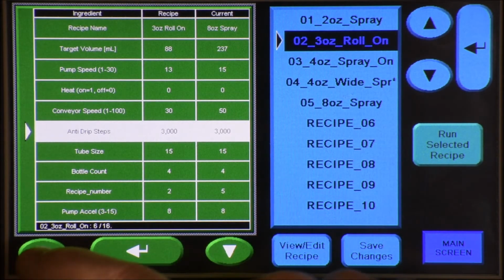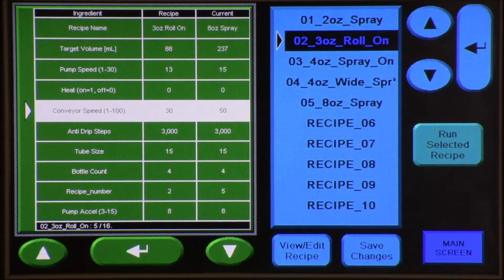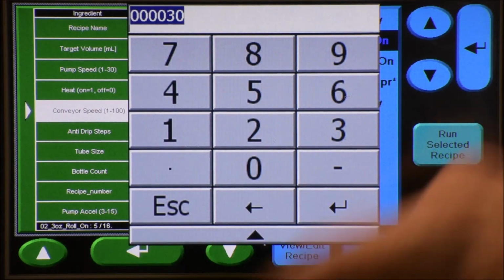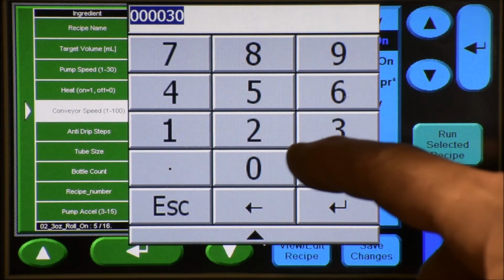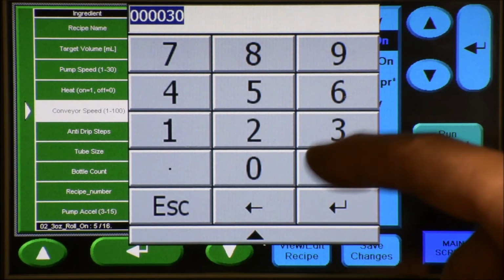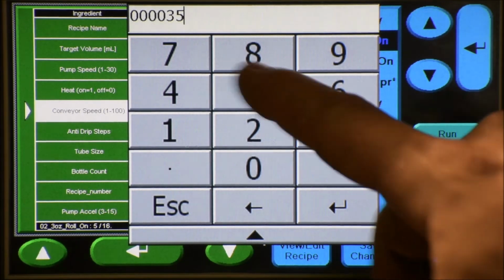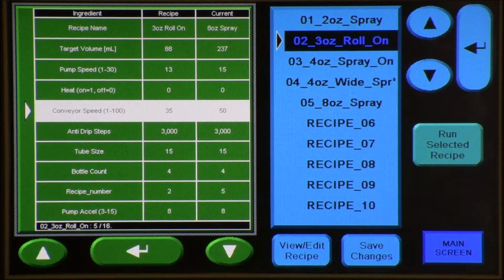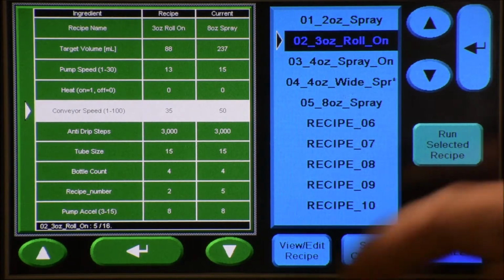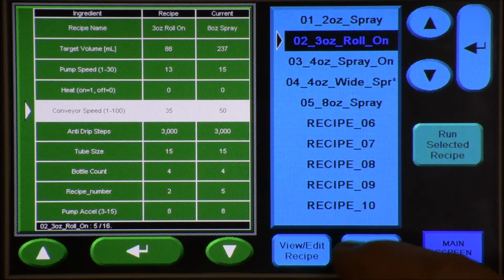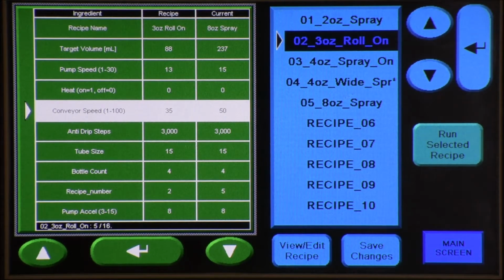So if I want to edit the conveyor speed on this recipe number 2, I'll highlight conveyor speed, hit enter. Right now we're at 30. That's a percentage out of 100, so let's take it to 35. Hit enter. I've now changed the value, but I need to save any changes I make. So I'll hit save. It's now saved any changes I've made. And then if I want to run this recipe with it highlighted here in this column, I hit run selected recipe.